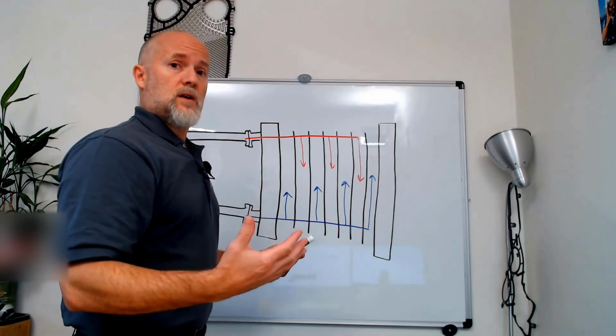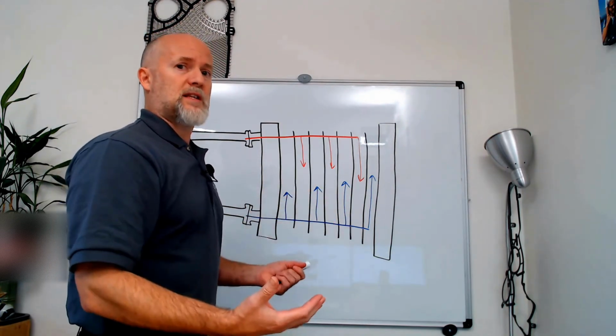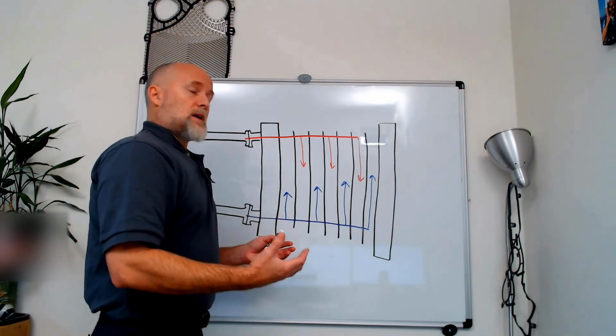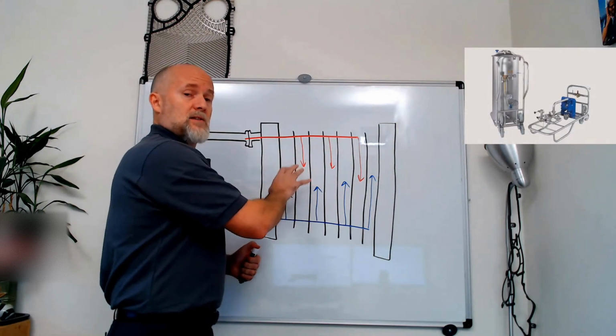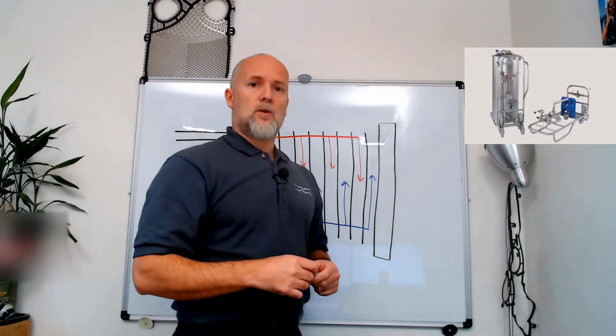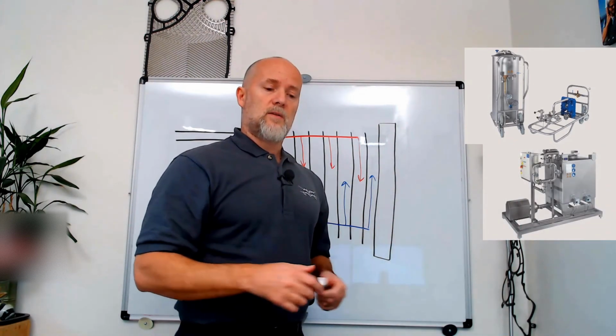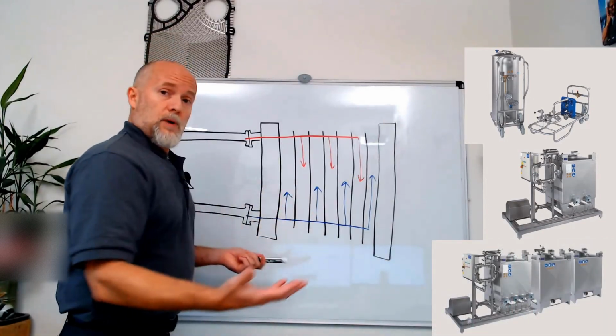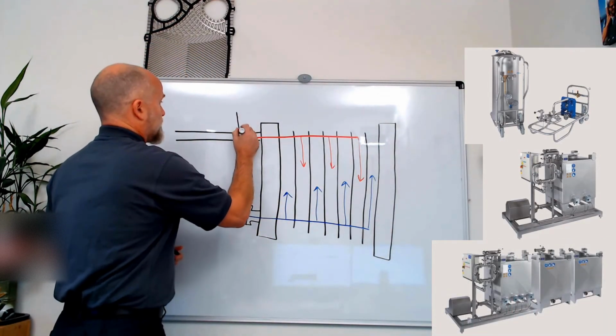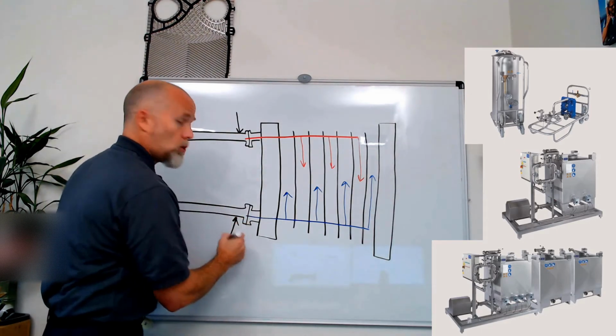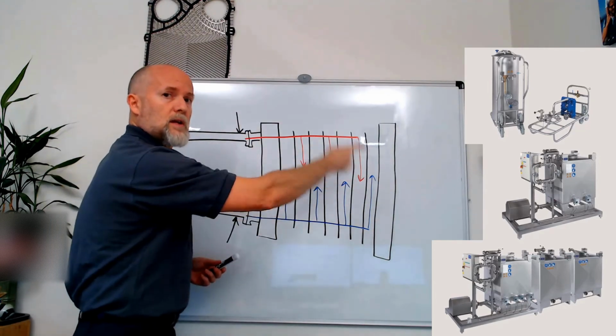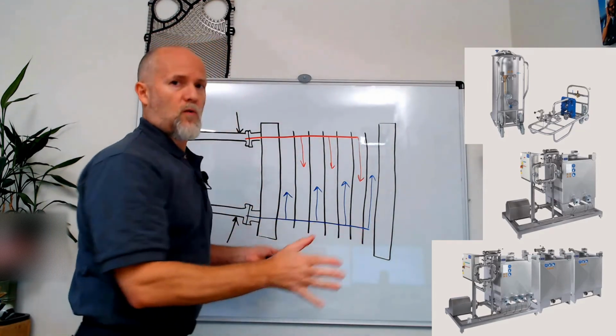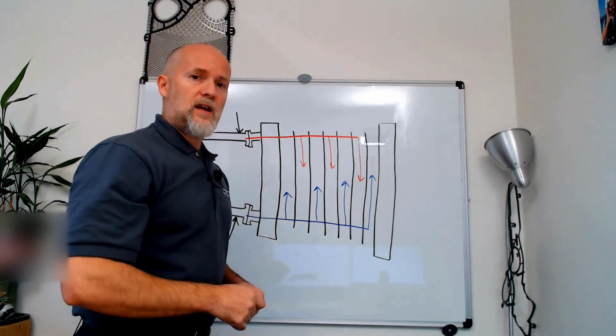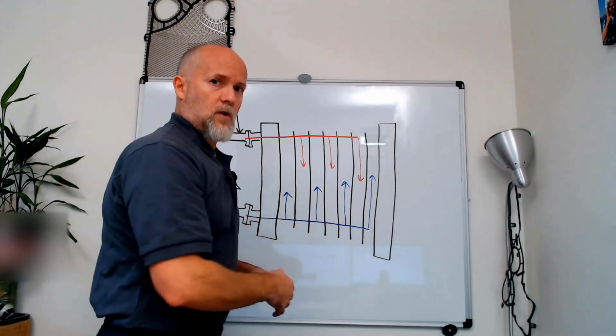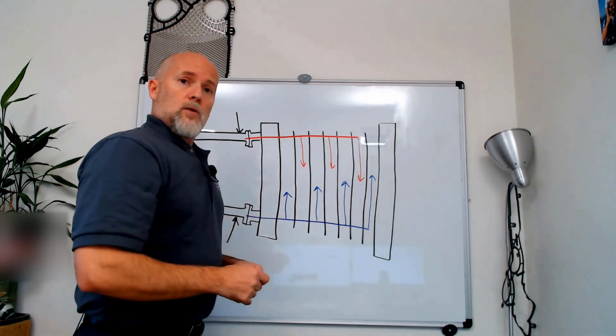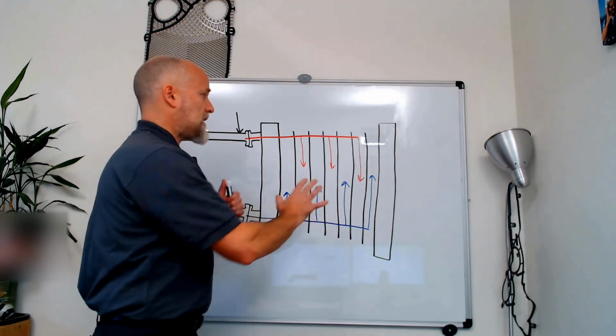So it's a cart with tanks and pumps, so everything is self-contained, with special chemicals that are designed to not harm the gaskets. So it's always a good idea to get your CIP cleaning solutions and carts from your vendor. But in practice, how it works is that you connect the hoses here and here, and then you run this cycle in a loop for a couple of hours. Of course, you have to close the valves and drain the heat exchanger from the water of your system. But then you run this cycle, and if it's not too dirty, it cleans the channels.